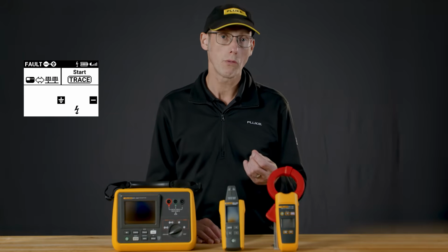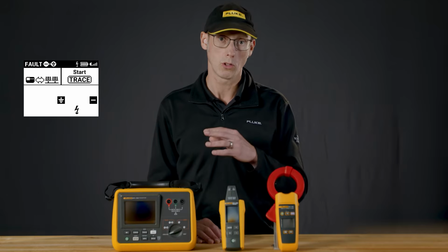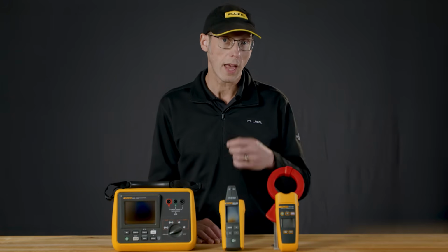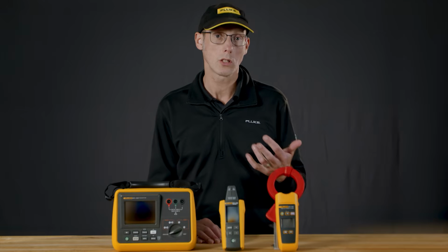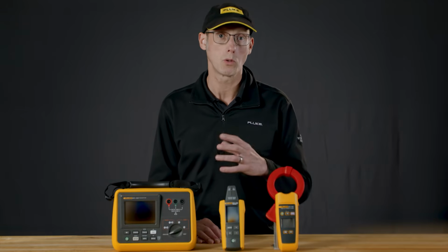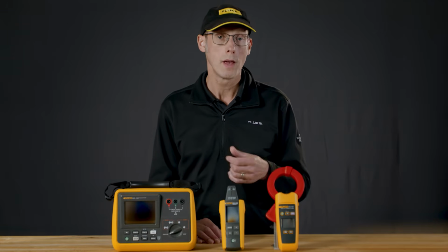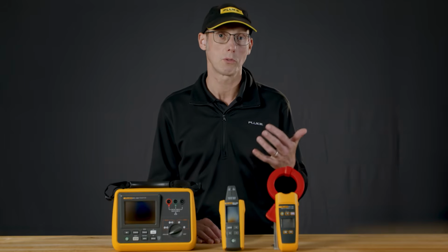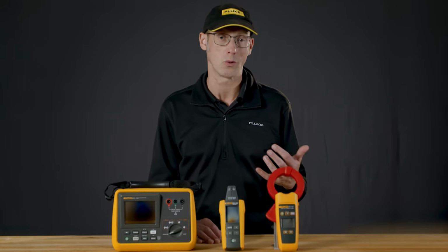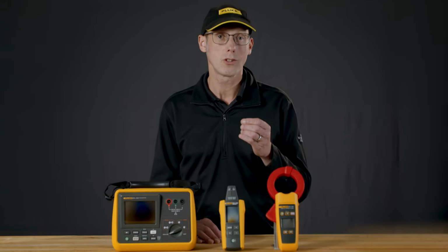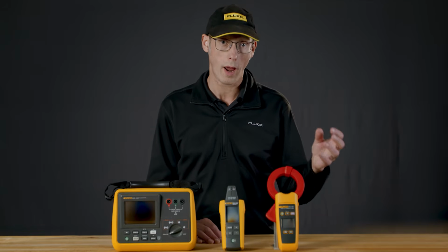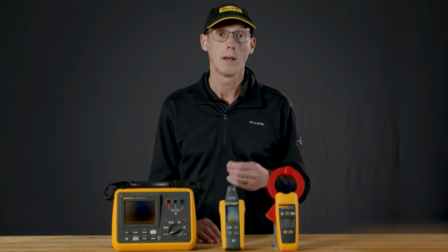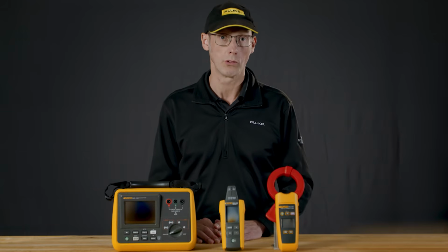There's also an auto feature that allows the transmitter to automatically select between array or unit. That can make it very easy for new technicians, where it will automatically switch between where the signal is sourced from. However, it can lead to some inconclusive results in certain types of array, especially high capacitance arrays. It's best to use either the array mode or the unit mode and manually switch between the two. That will give you the most consistent results.